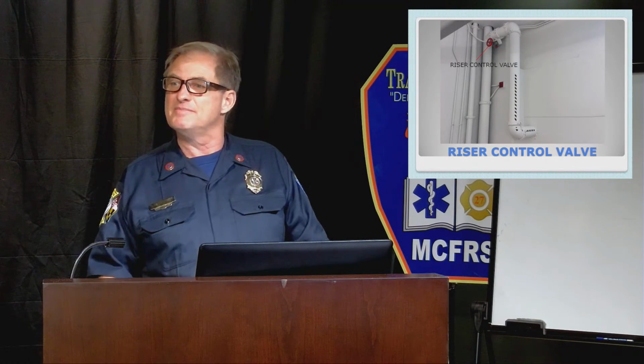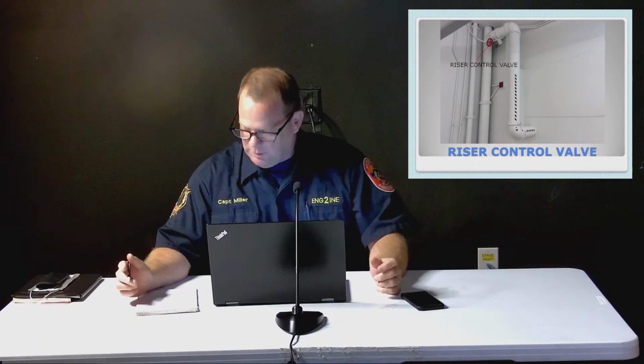Yes? So we actually have 2 questions, Chief. Yes. One of them is from me. So you showed a picture of the riser control valves. Are those valves always going to be located between the pump and the riser? Is that where we look for them in buildings? Yes. So your best bet to find them is to go into the stairs, locate the standpipe riser, and then find a pipe that comes off the riser that's either the same size as the riser or bigger than the riser. That is your bulk feed main. Somewhere between either inside the stairs and outside the stairs, but in that vicinity will be a control valve that allows you to isolate that riser.